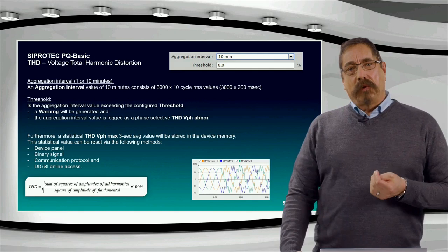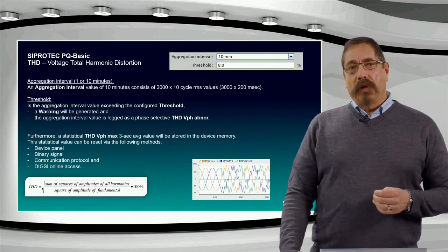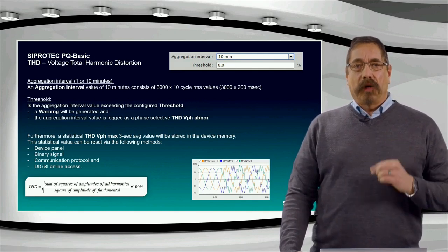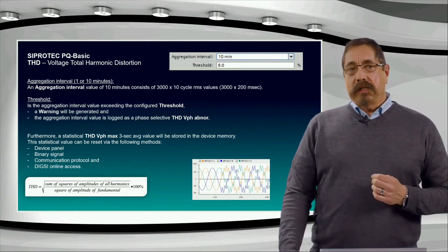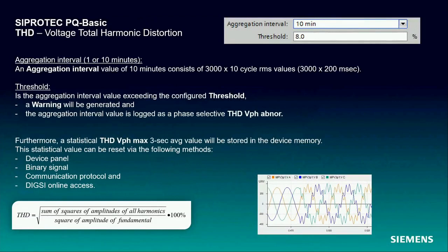From a power quality perspective, the total harmonic distortion is an important quality criterion. In the graphic on the right side down, you can see how a sine shape looks when the harmonic level is too high. The result could be that electrical infrastructure sporadically produces malfunctions like resets or overheating of equipment. The formula for the THD you can see on the left.